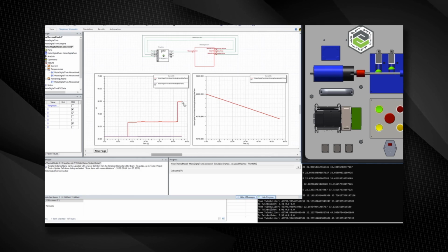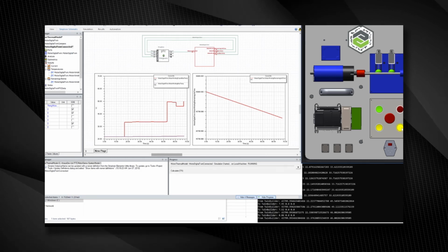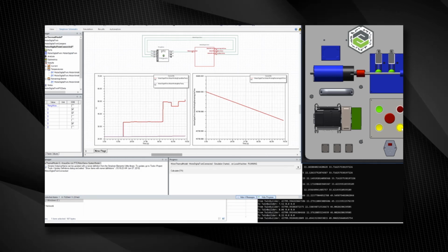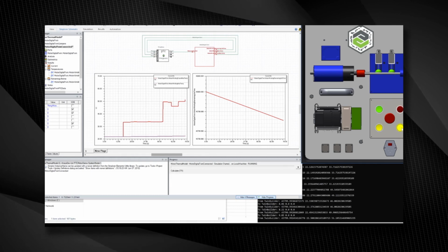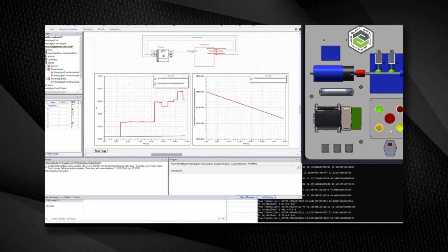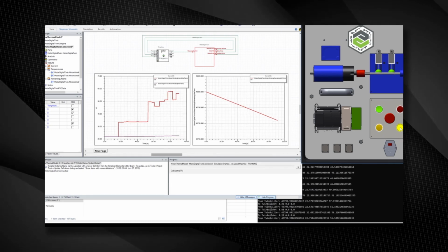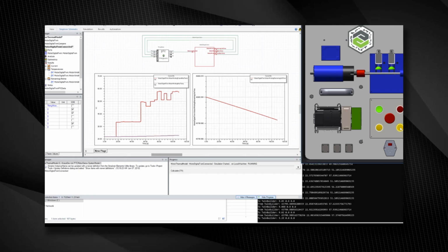Now, we can validate the digital twin. To do so, we need to gather information from the actual motor through PTC Thingworx. We start the PTC Thingworx agent and run the simulation in TwinBuilder. Information on current from the physical asset is sent to TwinBuilder, where the simulations are run to determine the current temperature of the motor along with the future temperatures. On the left, we can see the future temperature calculation in red and the ambient temperature in purple. This information is passed back to Thingworx.